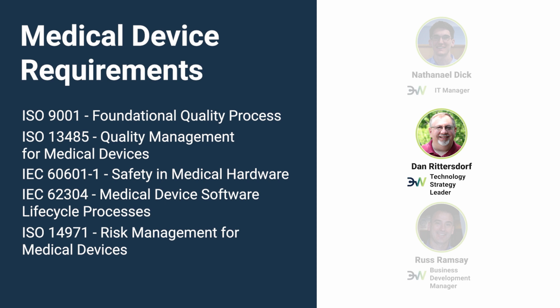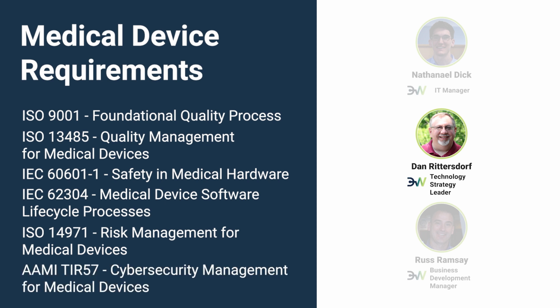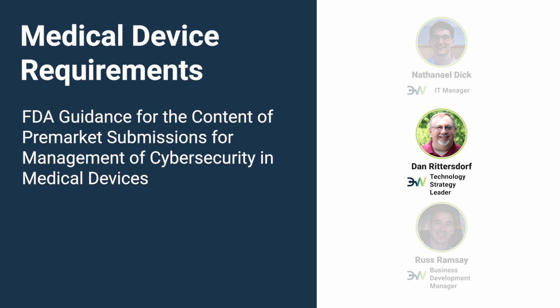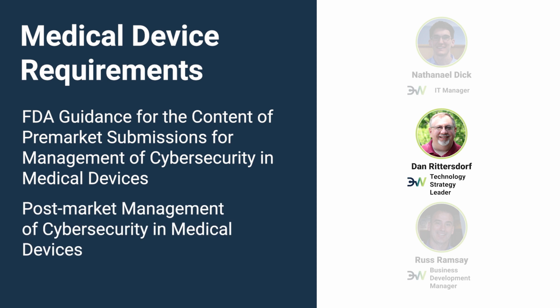And this pairs with AAMI TIR57, Principles of Medical Device Security, to provide a similar process for managing cybersecurity for medical devices. And then the FDA guidance document on content for pre-market submissions for management of cybersecurity in medical devices. There's a draft guidance right now that's looking to be certified or approved later this year. And then post-market management of cybersecurity in medical devices. The 2016 standard, the final guidance is out there and is relevant to medical devices today.